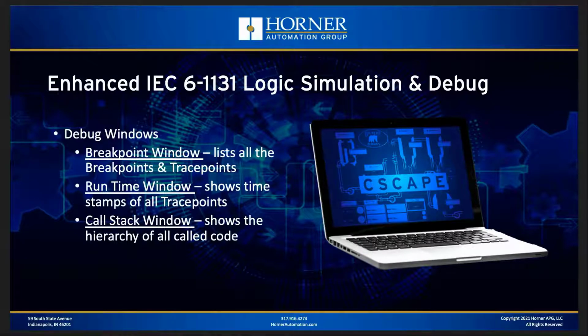And then there's also a call stack window. So if you are in step-by-step mode, it will show you specifically what routine is running and what line in that routine is running. And if that routine calls a subroutine, or a UDFB for instance, it will also show at a lower level what line of the subroutine is being executed. And then once that's complete, of course, it'll go back up to the routine that called the subroutine. So that can be really useful for taking a look at how your calls stack up from your main line code or your main routines to your subroutines and your UDFBs and all that sort of thing. So those are all great tools for being able to simulate and debug your program.